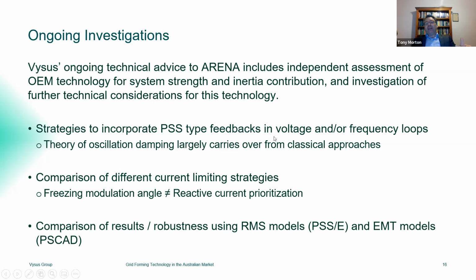So one thing here is we do want to see PSS type feedbacks being incorporated into these control systems. Fortunately, we know all about the theory of oscillation damping for synchronous machines, and most of that will carry over to virtual machines in grid forming converters. We look at different current limiting strategies. It's not necessarily the case that you get the best response to faults from grid forming plants just by prioritising reactive current, the way that we've been doing with our grid codes at the moment.